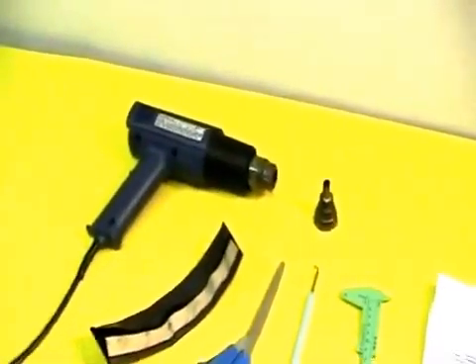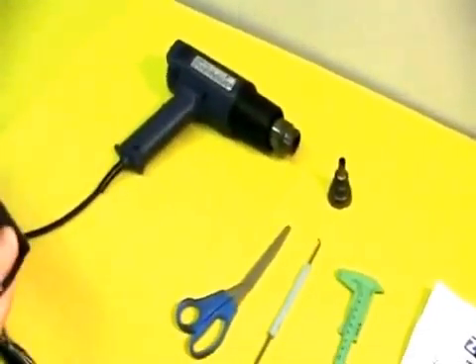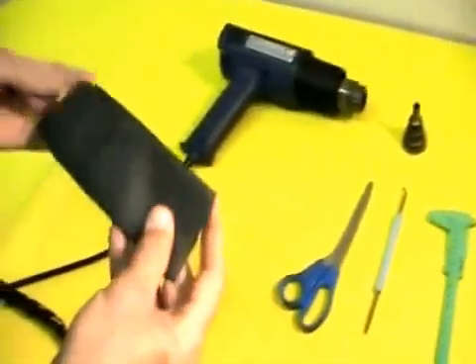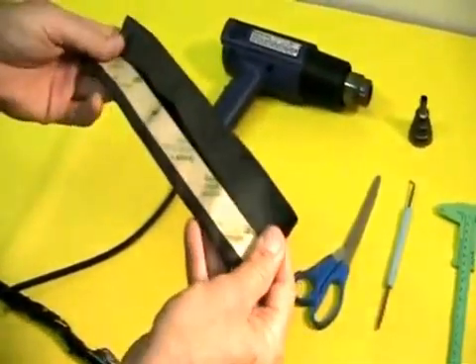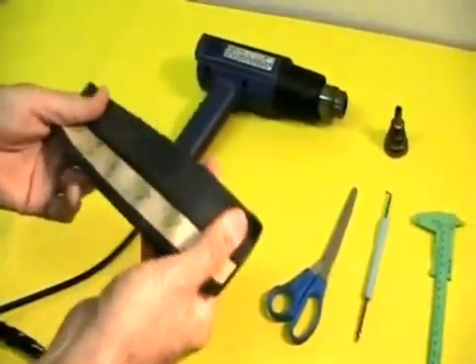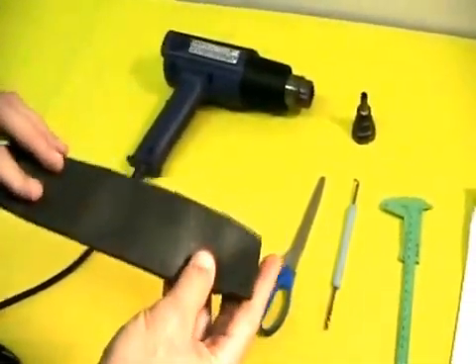You would like to have a heat gun that can generate around 150, 140 to 150 degrees C. The tubing begins shrinking at around 90 degrees C and will ultimately shrink quite well in the 120 to 130 degrees C range.